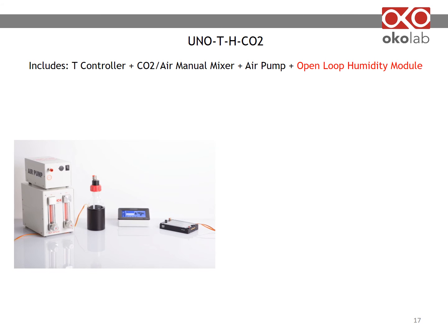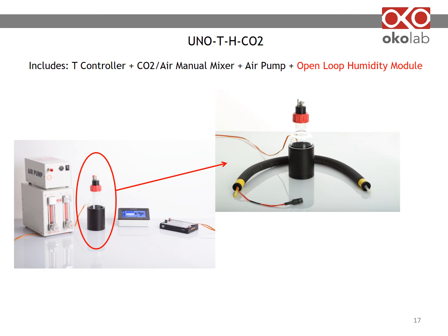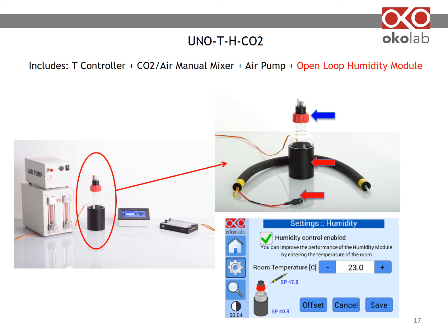UNO THCO2 includes a humidity module with a heated base, a glass bottle with lid, and heated and insulated tubing. To operate the humidity module, simply enable it by checking the box and input room temperature. The system will automatically set the temperature of the heating base and heated tube, optimizing humidity performance.